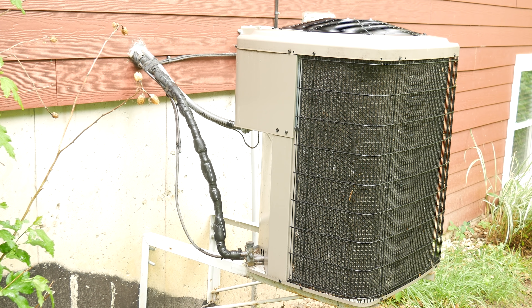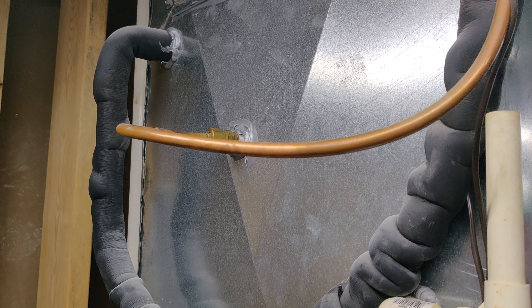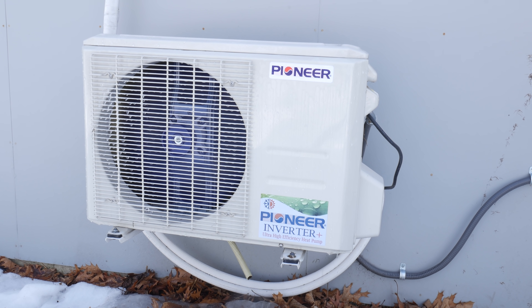You've got a nicely insulated home and are looking at replacing your whatever with a heat pump — what does that look like? The equipment in a heat pump consists broadly of three parts: the outside unit, which absorbs heat from the outside air; the inside unit or units, which put that heat where we want it; and the refrigerant line set or sets that connect them together and carry the refrigerant and its heat energy from place to place. Sometimes this is all packaged into a single device, but more often they are split systems. This is a single-head ductless mini-split heat pump, and it is the simplest possible split system.